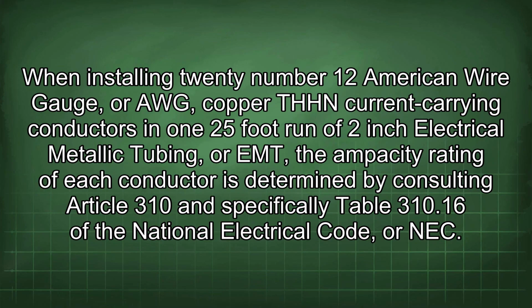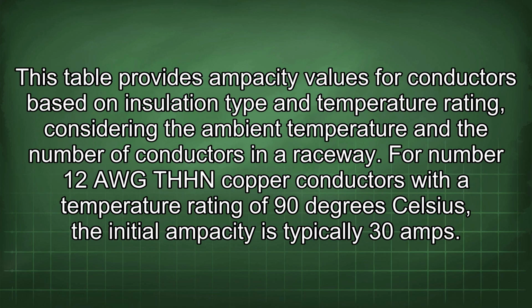When installing 20 number 12 American wire gauge (AWG) copper THHN current carrying conductors in one 25-foot run of 2-inch electrical metallic tubing, or EMT, the ampacity rating of each conductor is determined by consulting Article 310 and specifically Table 310.16 of the National Electrical Code, or NEC. This table provides ampacity values for conductors based on insulation type and temperature rating, considering the ambient temperature and the number of conductors in a raceway.